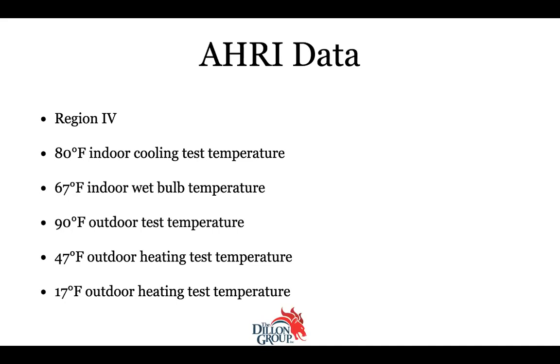where AHRI's headquarters is. 80 degrees Fahrenheit indoor cooling test, 67 degree indoor wet bulb, 90 degree outdoor temperature, 47 degree outdoor heating test temperature, and a 17 degree outdoor heating test temperature. Those are the test temperatures that they use. But those are the indoor conditions. Now, outside of me, in the summer, who keeps their house at 80 degrees? Nobody I know. No, I get an argument. 78, that's it. In the wintertime, nobody should be keeping their house at 80 degrees. There's no reason for that. But these are unrealistic test conditions, even for Arlington, Virginia, right? But this is where the data comes from.